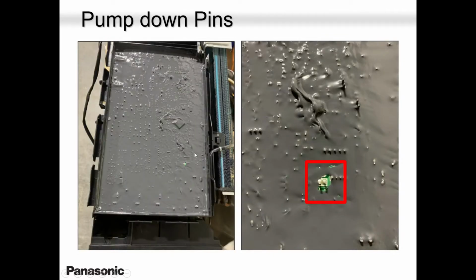Then when you're opening the board on top, you will see this section here. This is fully sprayed as a waterproof. This section was not sprayed because you can use these 2 pins to short it. And once you short it, leave it there. Don't touch it, leave it there. If you have alligator clamps or clips, jumper it to pump down the system. To pump down the system, which, if you're an experienced guy, can also tell you that the outdoor board is in good shape and the compressor is in good shape and you have a problem somewhere else. So you can use these 2 pins to pretend like you did a test run. But mind you, this was designed specially for pump down.